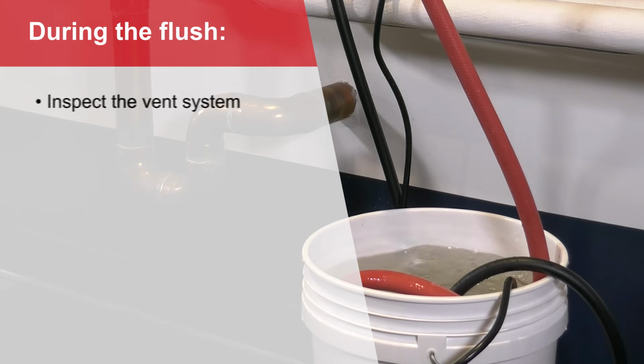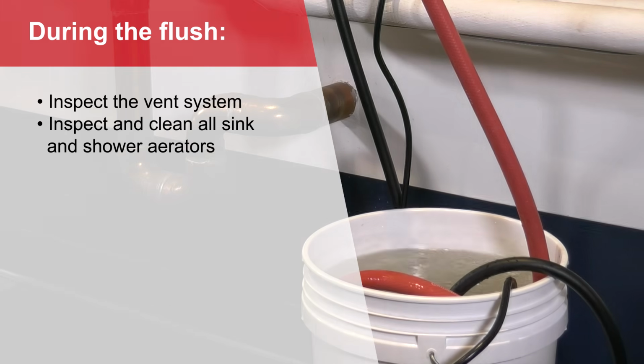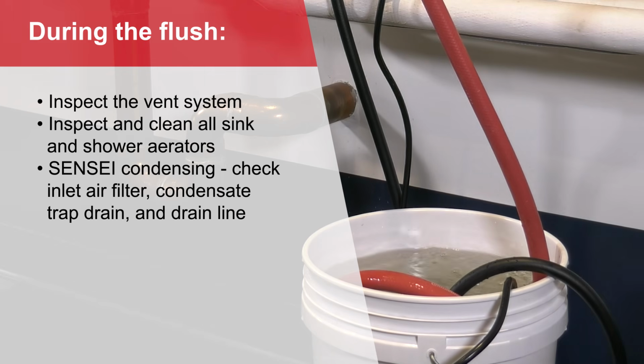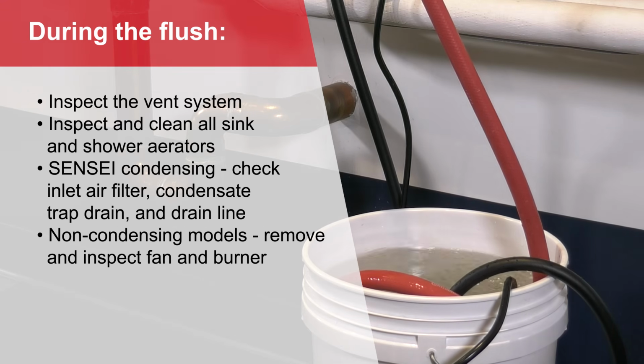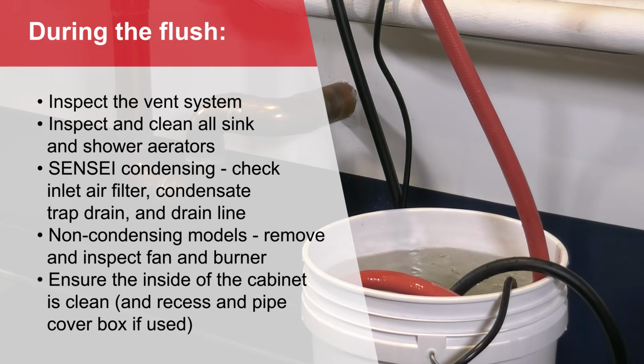On all models, inspect the vent system if possible, and inspect and clean all sink and shower aerators in the structure. On Sensei condensing models, check the inlet air filter and the condensate trap drain and drain lines. On non-condensing models, remove and inspect the fan and the burner, and ensure the inside of the cabinet is clean and the recess and pipe cover box if used.